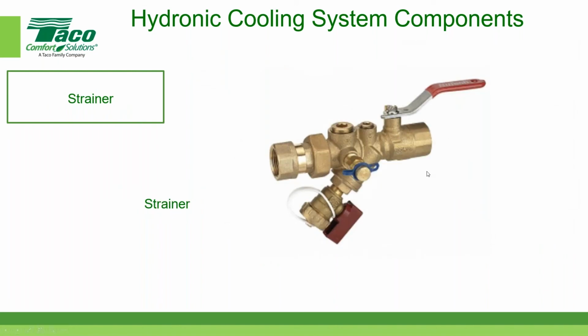And then the last one is the strainer. The strainer is used to remove particles as water passes through the piping system, usually to a coil. We don't want the coil to plug up with debris. The water would flow in this direction, exit over here, and there's a little strainer inside. You can't actually see it, but the water flows around, then out. It also has a hose bib cap right there, and then a blowdown valve so that you can blow down the debris as it collects over time. So those are the major components that you find in a hydronic cooling system.